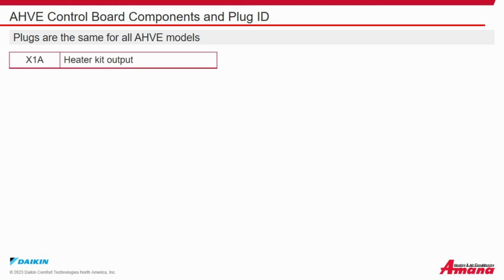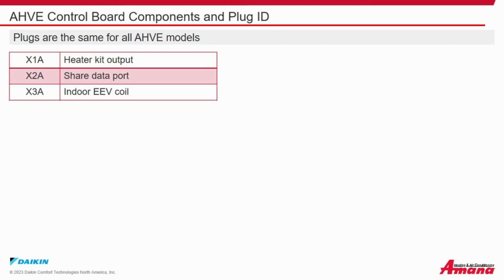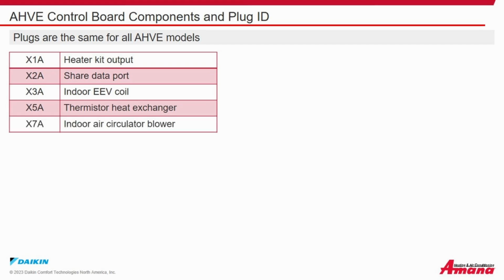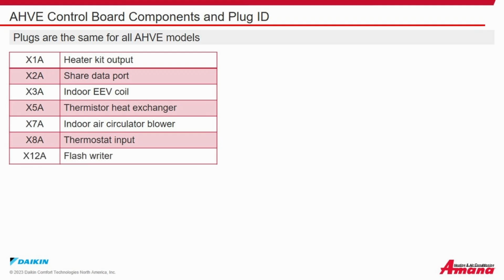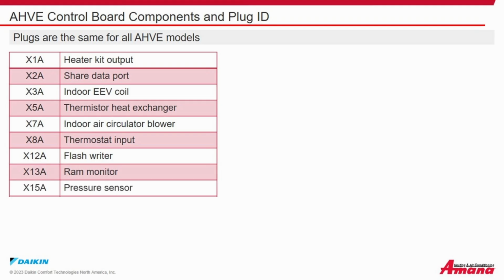X1A heater kit output, X2A shared data port, X3A indoor electronic expansion valve coil, X5A thermistor for the heat exchanger, X7A indoor air circulator blower, X8A thermostat input, X12A flash writer, X13A RAM monitor, X15A pressure sensor.